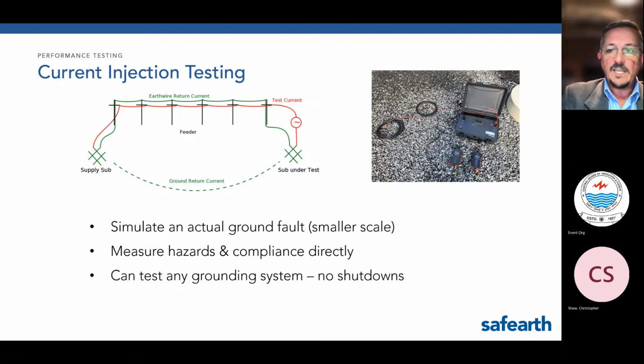In current injection testing, a small test current is circulated around a test circuit. The test circuit can be an overland lead passing current to simulate a fault, or the test circuit can actually include the injection of current over a power line or a cable. Being small, this current can be allowed to flow for hours while measurements are being taken.